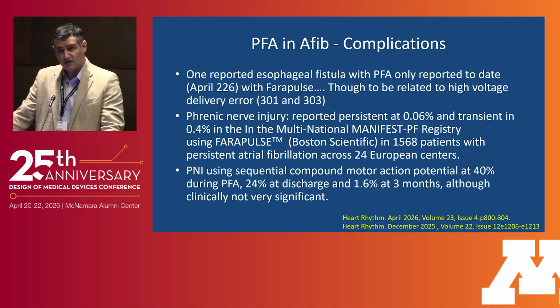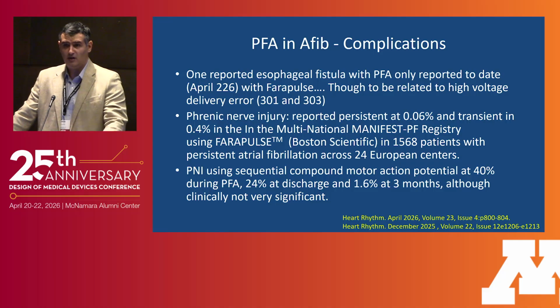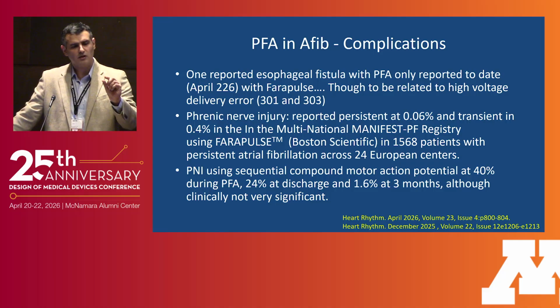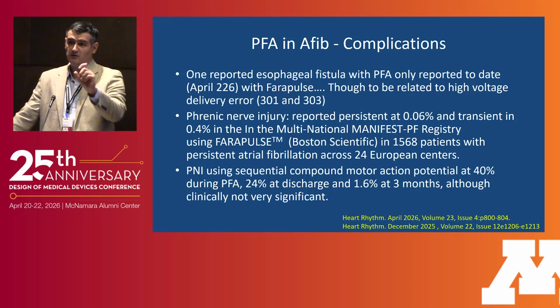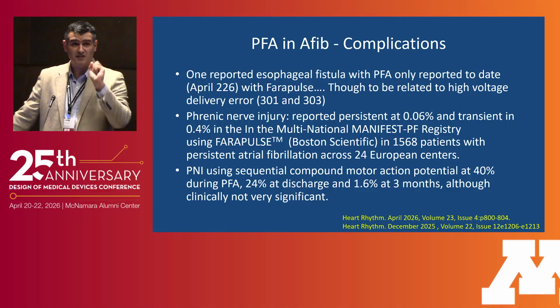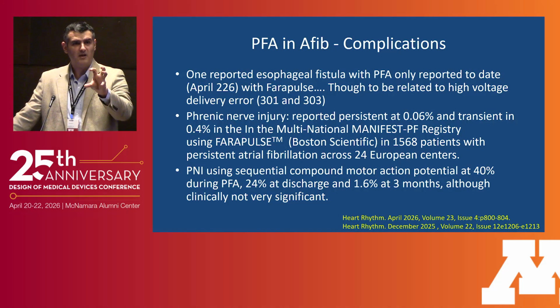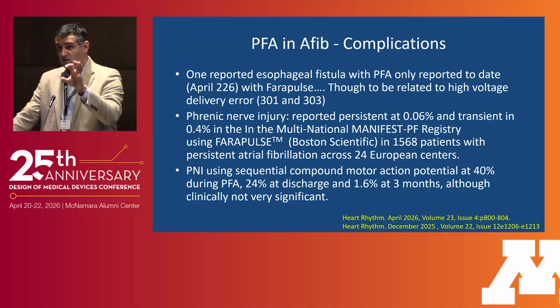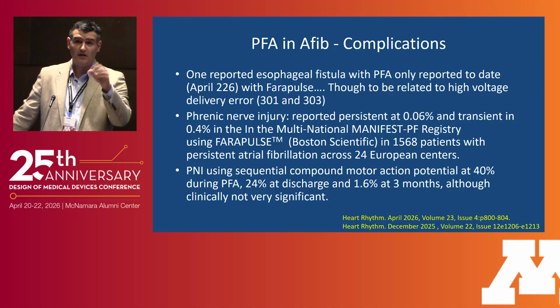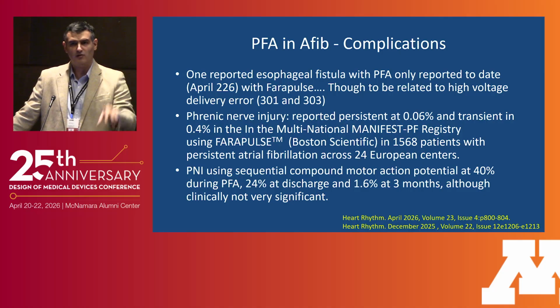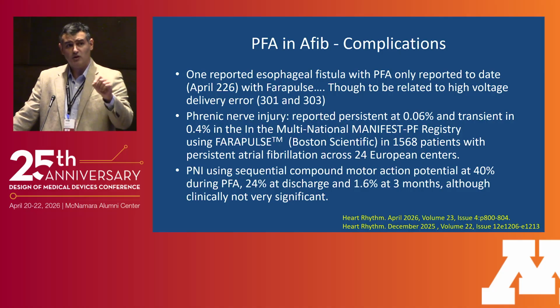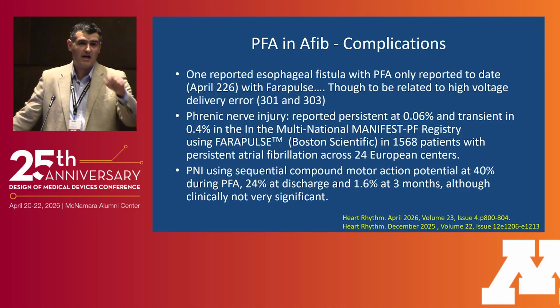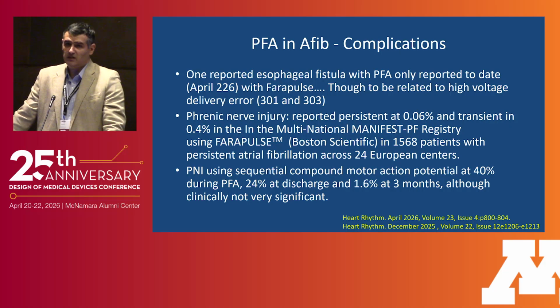During that case, they had a generator glitch where two splines got too close together, causing very high energy delivery. Normally there's a fail-safe in these generators that stops delivery and alerts you that the splines are too close and need to be separated, otherwise current levels get too high. They had two or three such events reported in one area of the heart, and the esophageal fistula formed in that same area where high energy delivery had been flagged and stopped by the generator.